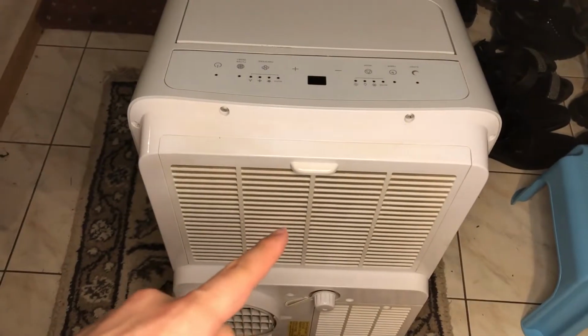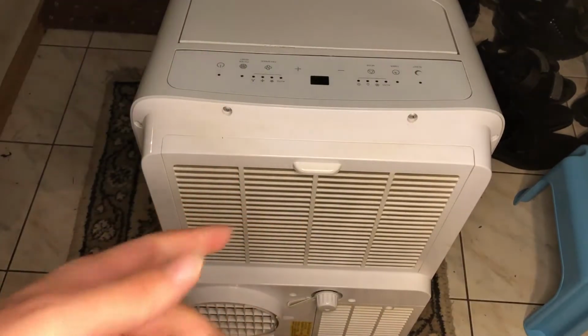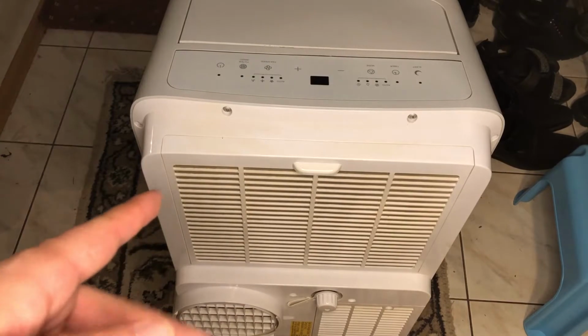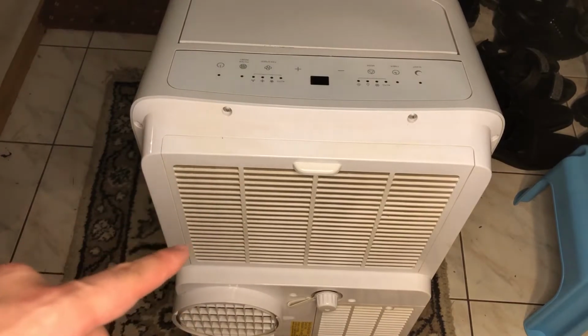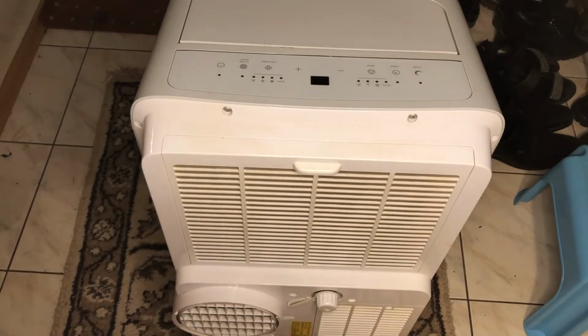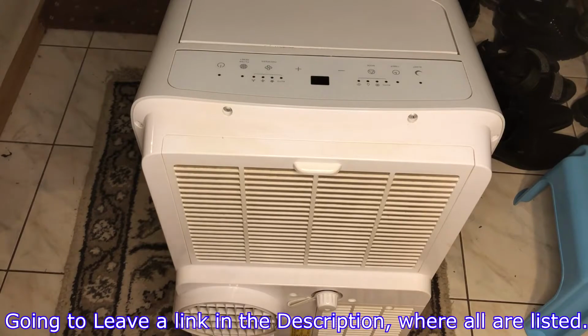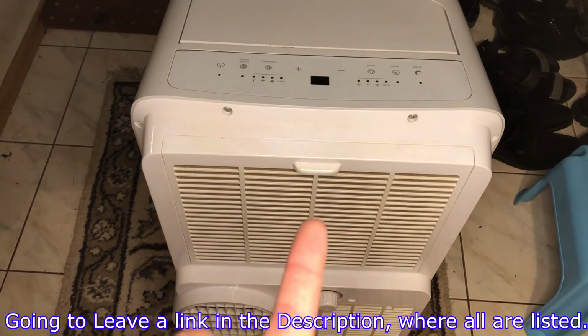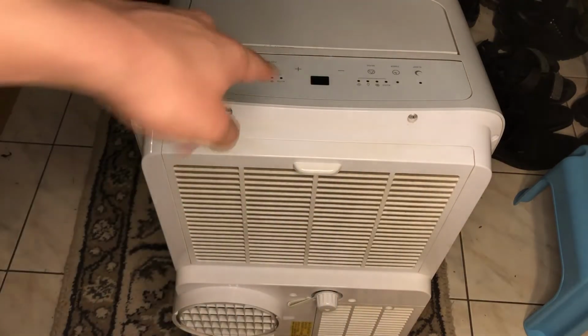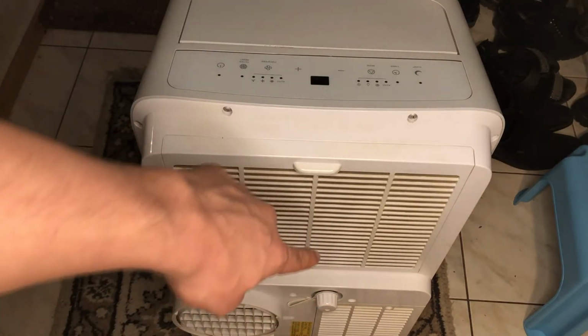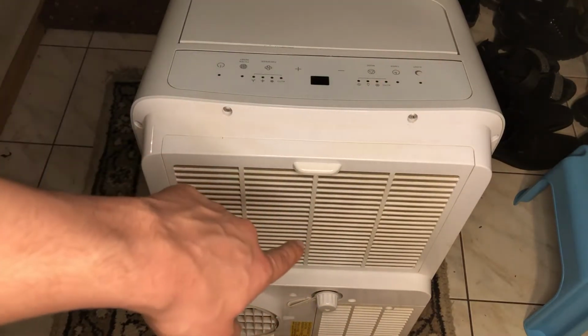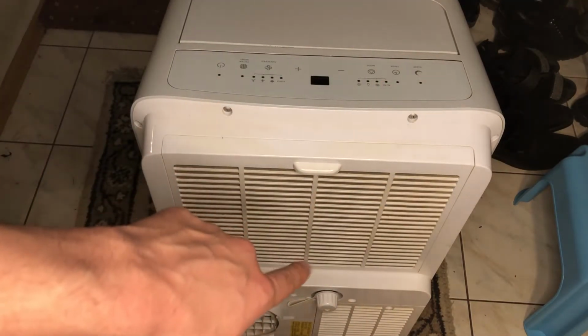What causes this issue? The code E8 is thrown by about 5 different problems. I'm going to probably insert them here because I don't remember all of them. A couple of them are: if one of the two fans, like the upper or the lower fan, isn't spinning fast enough or is out or broken.